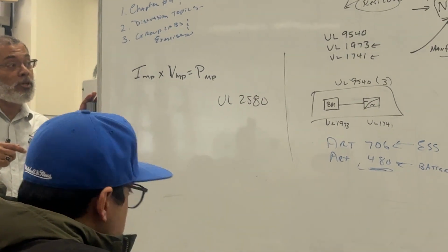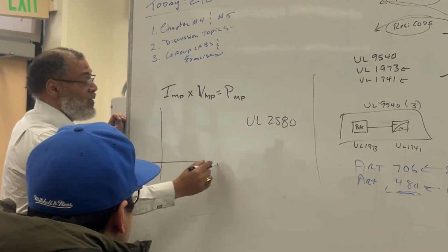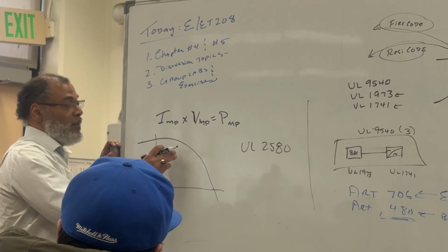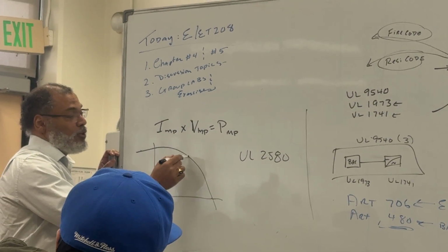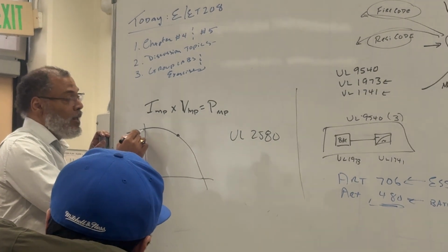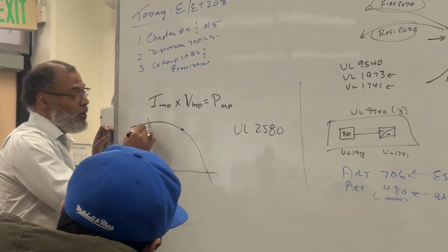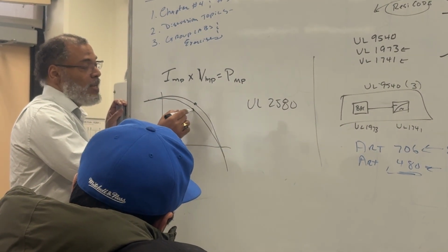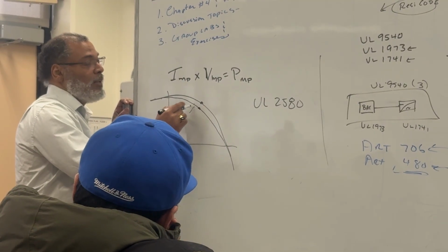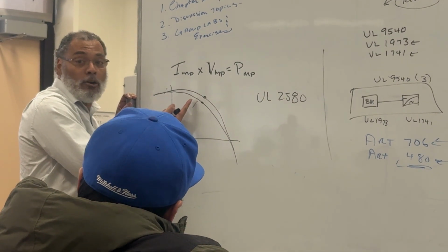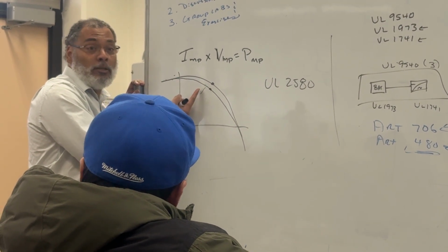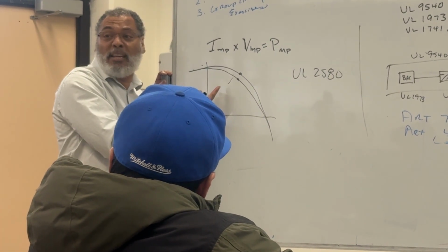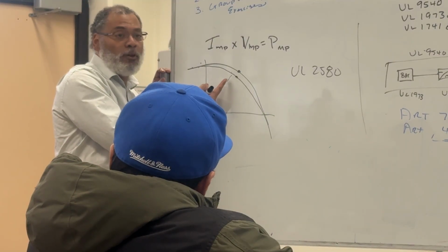So when you start talking about IV curves and this fill factor, the IV curve looks kind of like this, right? That's a nice curve that has a nice sharp peak on there. But then when you look at the same curve, and if it looks like this, then it's not as sharp and it's not filling the entire curve. And so that's the ideal. And so most modules fill in about 70%, 80% right now, that fill that curve.